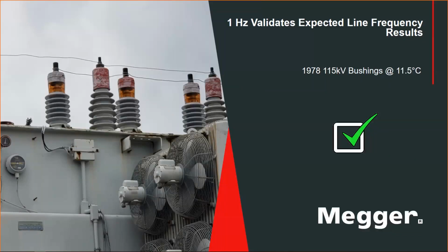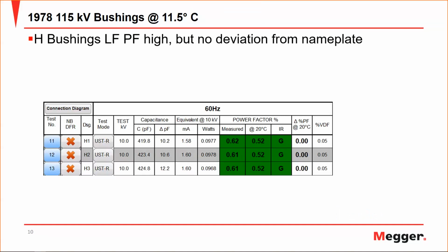So the first example that I'm going to give is going to be for a 1978 transformer with 115 kV bushings tested at 11.5 degrees C. And when we look at this result, we see that the H bushings, their line frequency power factor values are high, but there is no deviation from the nameplate in terms of capacitance or percent power factor. So we really have no concerns about these particular bushings. But again, if we only had line frequency power factor, we may not be able to be so confident in this assessment, and for reasons you will see later on.